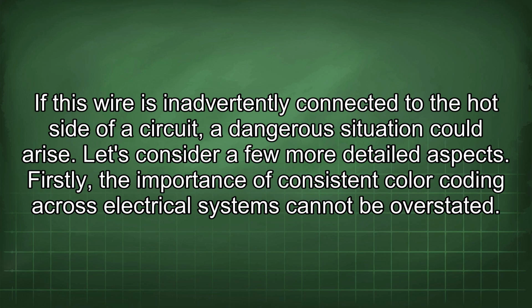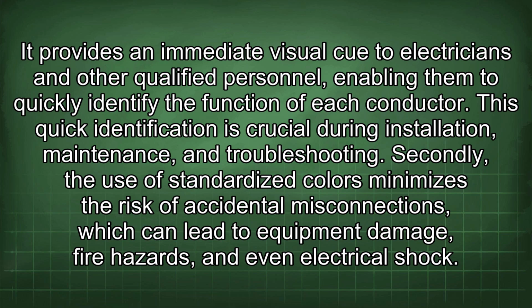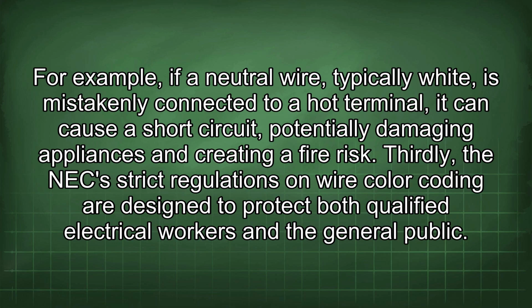Let's consider a few more detailed aspects. Firstly, the importance of consistent color coding across electrical systems cannot be overstated. It provides an immediate visual cue to electricians and other qualified personnel, enabling them to quickly identify the function of each conductor. This quick identification is crucial during installation, maintenance, and troubleshooting. Secondly, the use of standardized colors minimizes the risk of accidental misconnections, which can lead to equipment damage, fire hazards, and even electrical shock. For example, if a neutral wire, typically white, is mistakenly connected to a hot terminal, it can cause a short circuit, potentially damaging appliances and creating a fire risk.